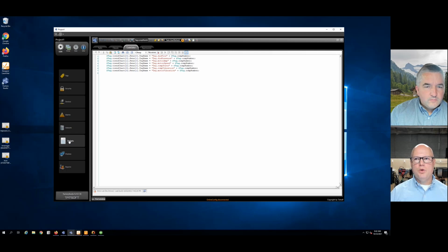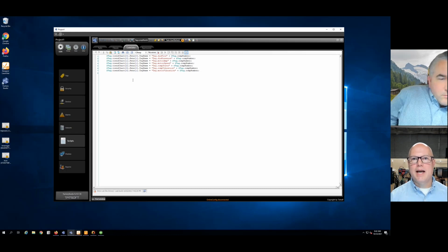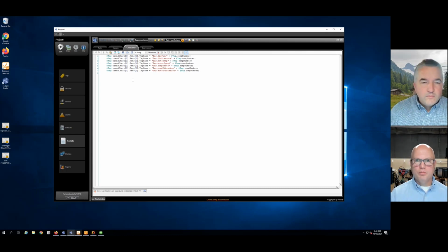So when I have a view, I have to create an instance for everything that I'm doing there. One of the things that I'm using is part of their scripting engine, and I'll break this down a little bit, but fundamentally, to get those tags done dynamically so that I can have compressor 1, compressor 2, I've had to name the chart itself and the pen. So we're going to get a little into the weeds here, so stop me when things aren't making sense, and then we'll walk through exactly what it is that we're doing here.